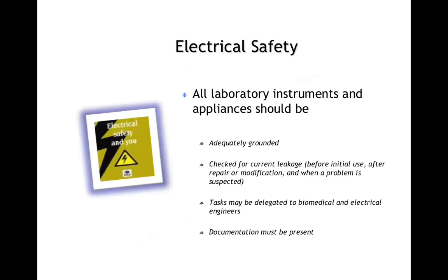Electrical safety is important. Appropriately grounded. Check for current leakage before initial use or after any repair, or whenever a problem is suspected. And you follow general guidelines like multi-plug shall not be used to fix multiple plugs in one socket. You shall have a sufficient number of sockets.